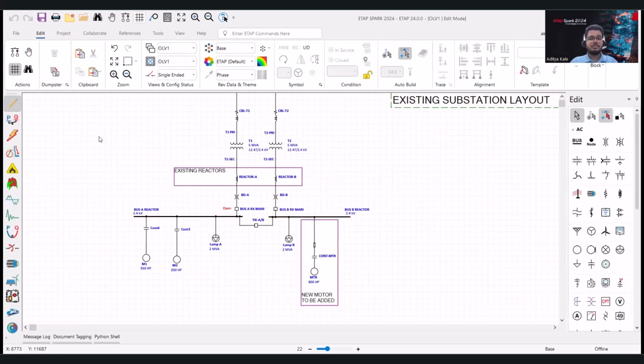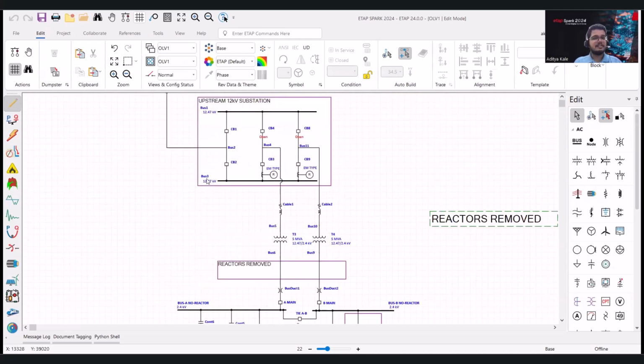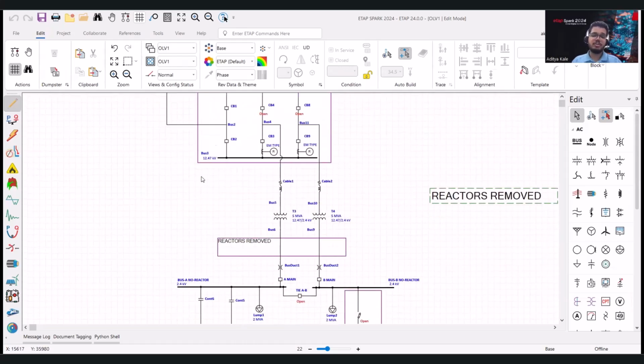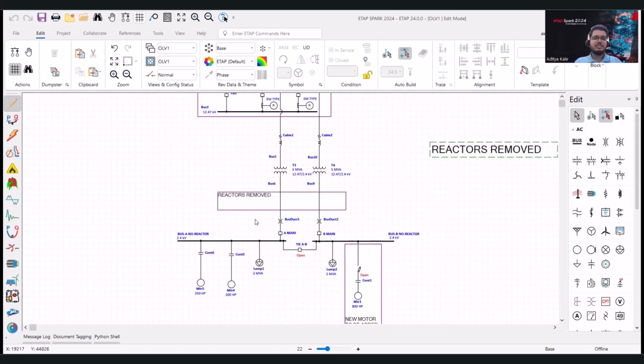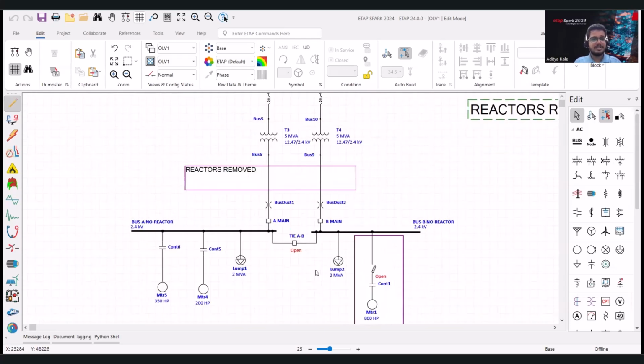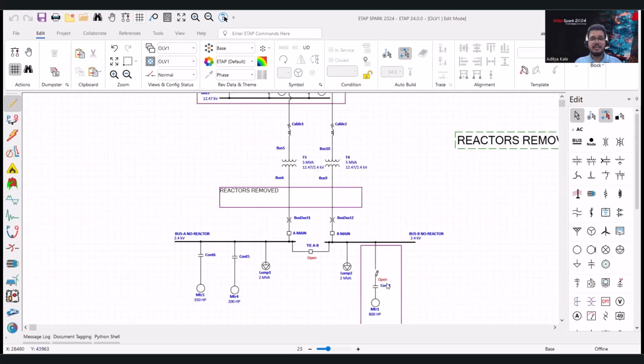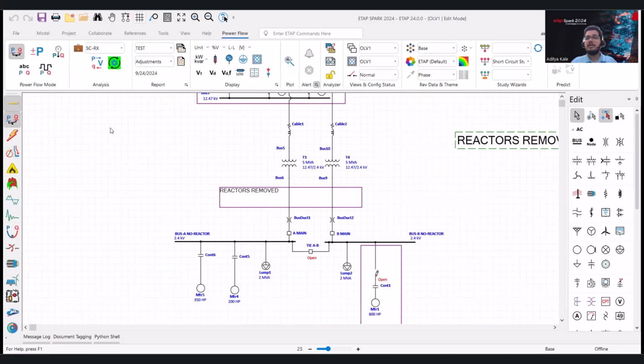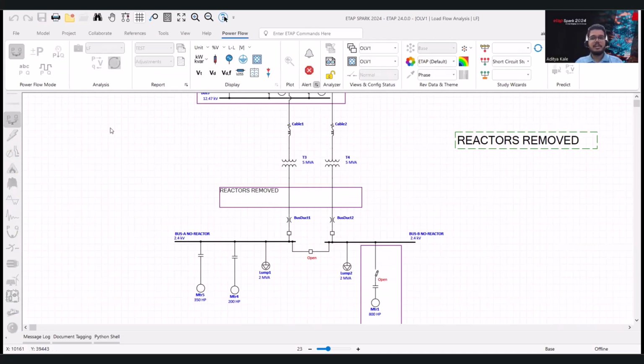So an obvious solution to this one, we just take the reactors out. That takes us to Model 2.0, where we have the exact same substation, but the reactors are removed. The buses are renamed to Bus A and Bus B, no reactor. Let's take a look at the motor starting here. The load flow study. So we can look at the voltage in a normal configuration. We have the motor starting voltage at 97%, which is very healthy.